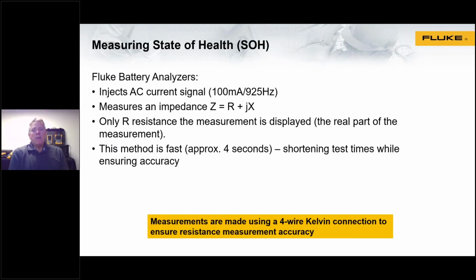The Fluke battery analyzers, which we'll be looking at in a little bit, use a technique to make this critical measurement and really only look at that resistive component. We actually use an AC current signal, and we are measuring an impedance, but through the measurement technique, we're able to extract just the resistive component, which really is the gold standard for determining the state of health of the battery. So it's really just the real resistance.